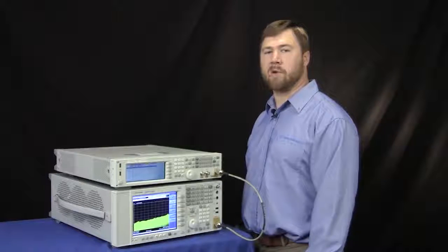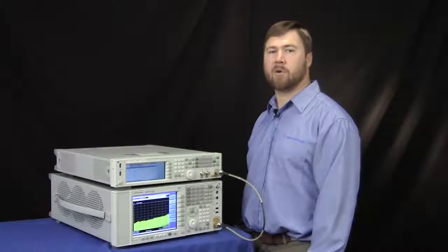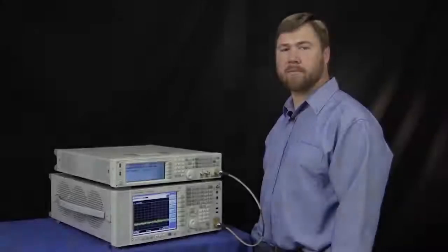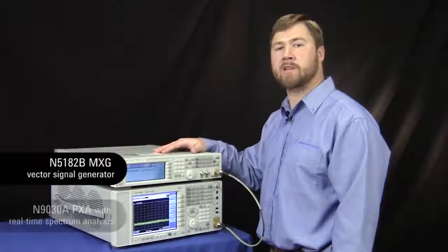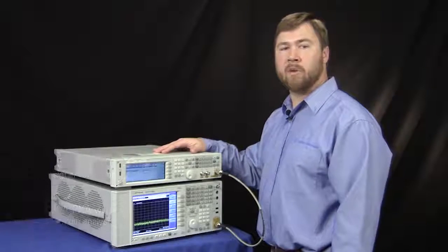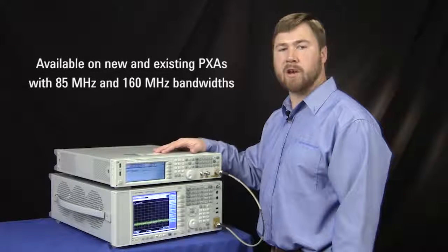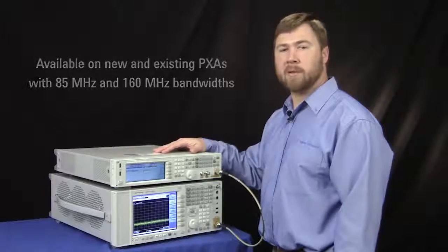First, we'll try to measure this signal in swept mode, then we'll switch to real-time spectrum analyzer mode. Let's get to our test setup. We've got an MXG vector signal generator and a PXA with real-time spectrum analysis. This is available on all PXAs with the 160 MHz bandwidth option, and also as an upgrade. Now let's make the measurement.